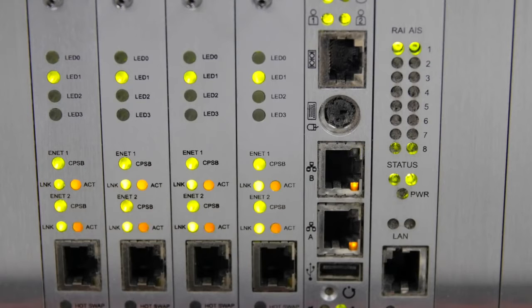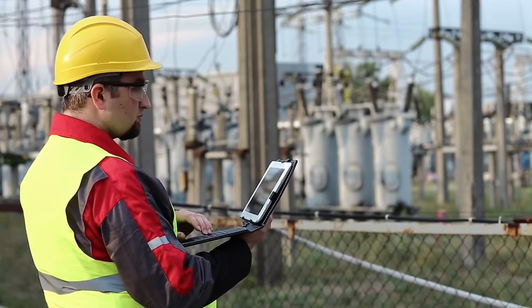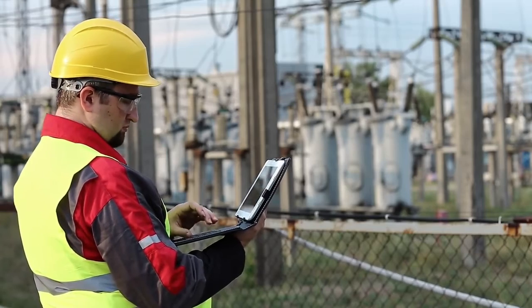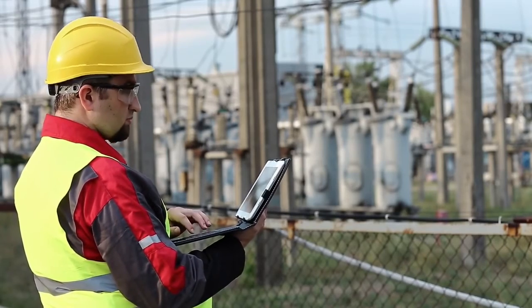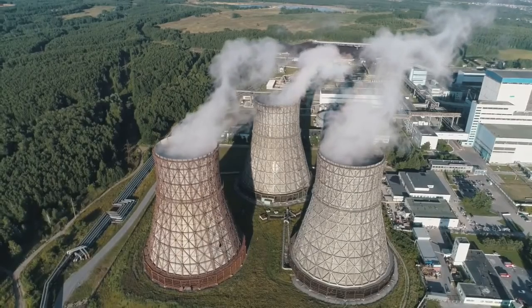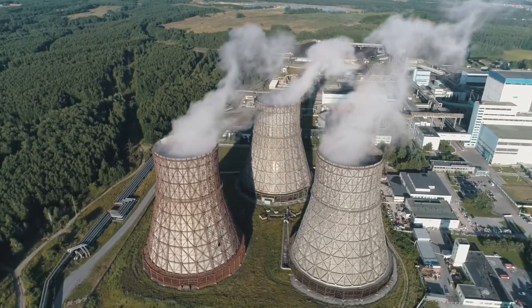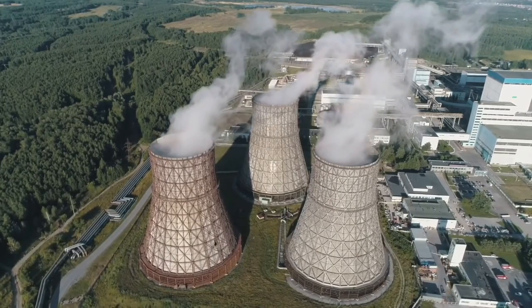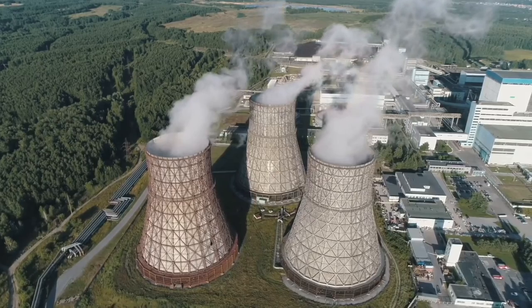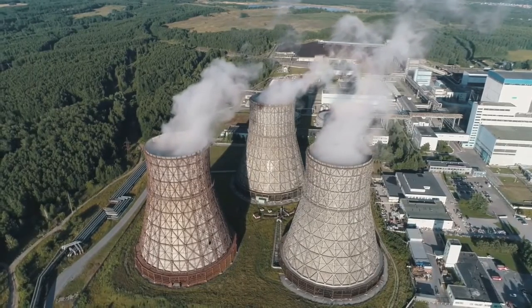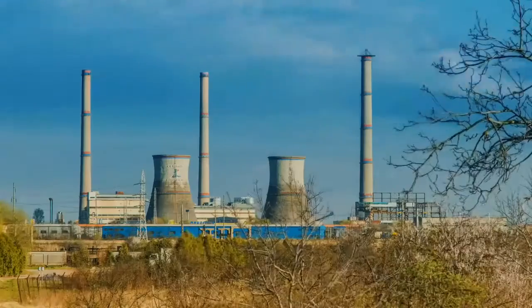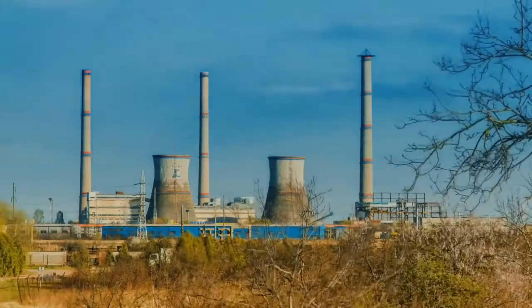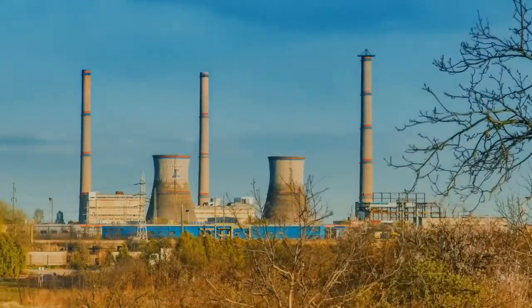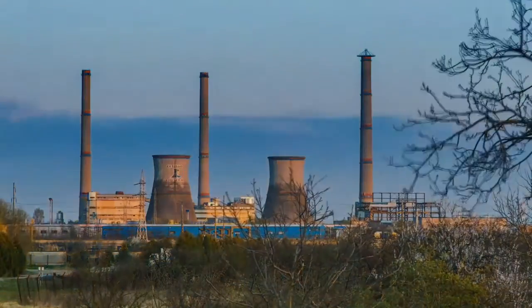Starting back up from a major blackout like this can be really complicated. Even just choosing which equipment to unisolate and in what order takes a lot of consideration and engineering. There's a chicken and egg situation because most large power plants actually need some power to operate, so it can be difficult to start back up during a wide area outage, also called a black start. But it's still better than the alternative of having to perform major equipment replacements because things spiraled out of control.